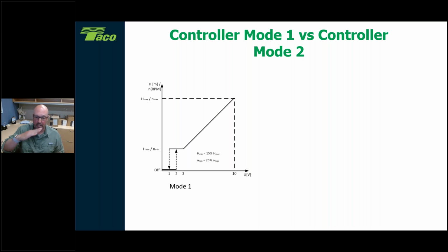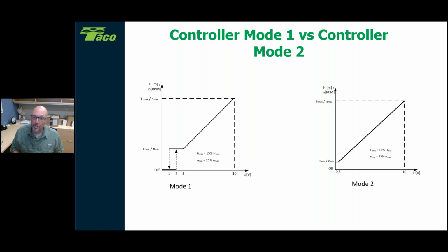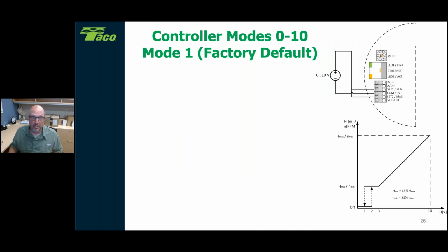Or actually, I should look at it this way if you're looking at the screen compared to what I see on the screen. Then mode number 2 brings us all the way down to half a volt, and then maintains a minimum speed of the circulator, never really shutting it off. So you have to know what signal we want to bring into the circulator based upon the equipment that's sending that signal. I couldn't tell you one versus the other. It's just coming from those manufacturers themselves what that device is telling us to do.